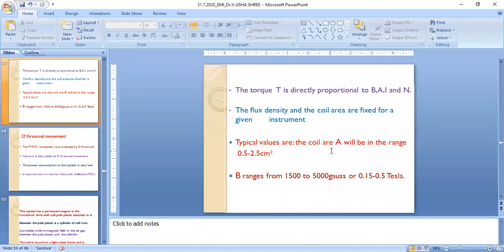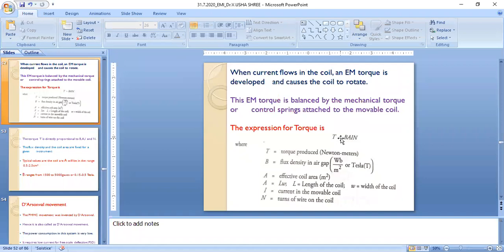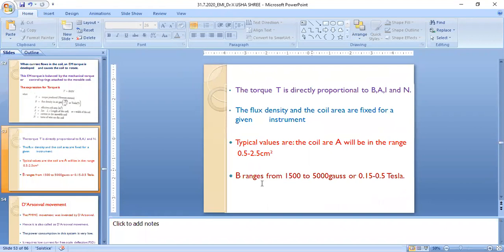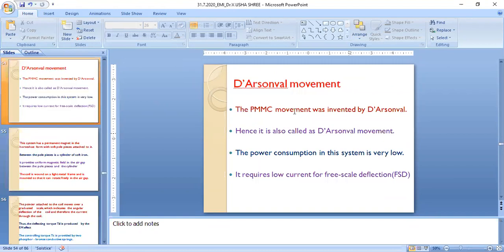The torque is directly proportional to flux density, effective coil area, current in the movable coil, and number of turns. The flux density and coil area are fixed for a given instrument. The typical coil area A ranges from 0.5 to 2.5 cm², and the flux density B in the air gap ranges from 1500 to 5000 gauss, or 0.15 to 0.5 Tesla.